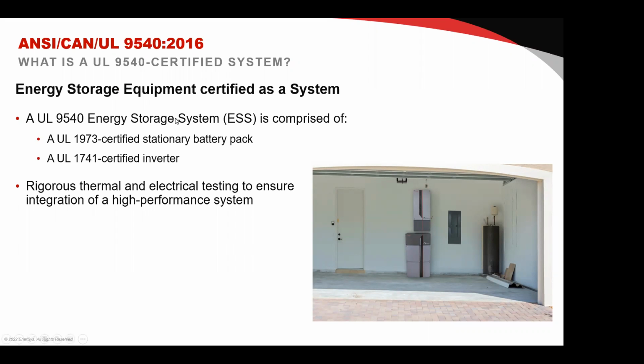From a regulatory standpoint, a UL 9540 energy storage system is comprised of a UL 1973 certified stationary battery pack. A lot of batteries, especially the AGM batteries, were listed under a different UL, like 1778 or 1989, but it is a UL 1973 and a UL 1741 certified inverter.